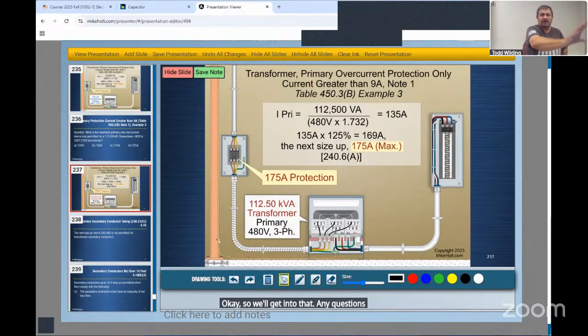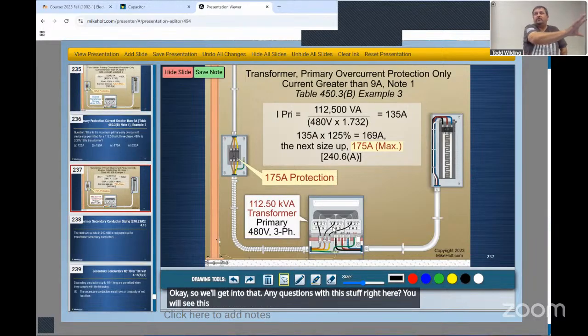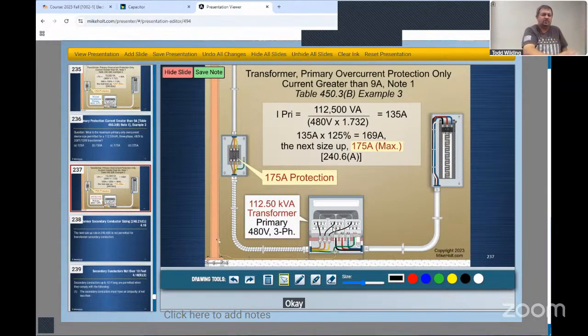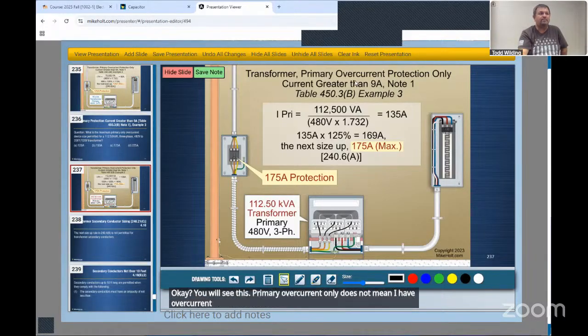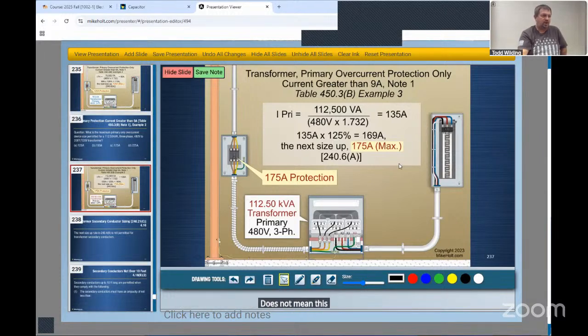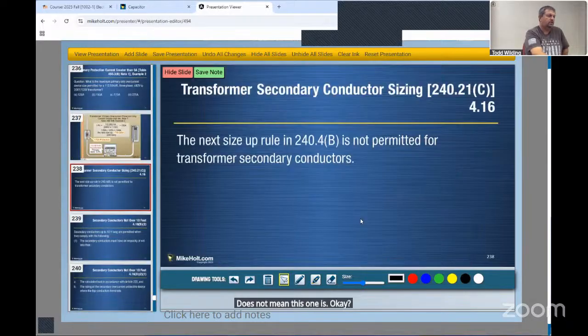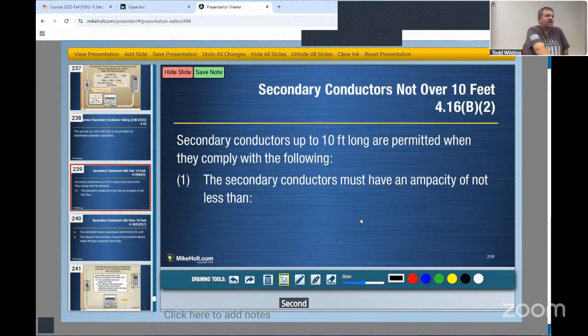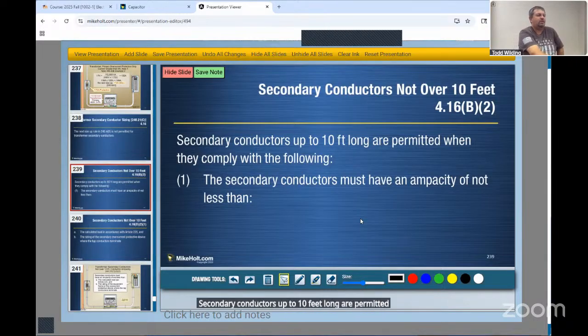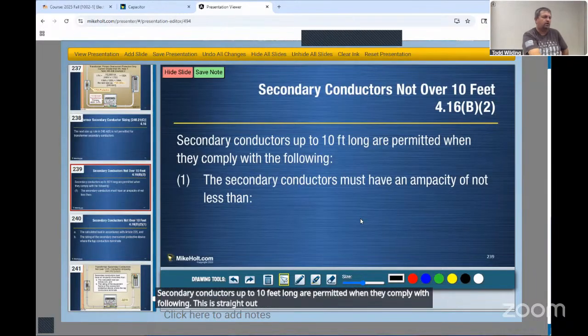Any questions with this stuff right here? You will see this out there in the field. Primary overcurrent only. It does not mean I have overcurrent protection here. This is primary only; it does not mean this one is. So the next size up is not permitted for transformer secondary conductors. Secondary conductors up to 10 feet long are permitted when they comply with the following. This is straight out of the code book in Article 240.